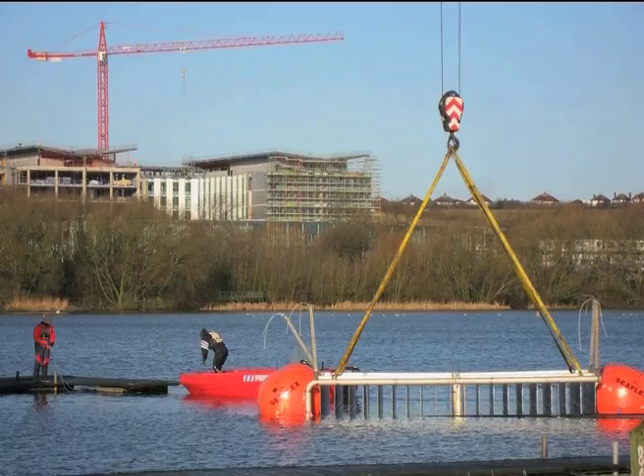Or in the summer, when the lake is cooler than the outside air temperature, it provides cooling to the hospital. It's very, very energy efficient, much more efficient than coal or oil or any traditional technology. Because for every 1 kilowatt of power that you put into the system, you get between 4 and 7 kilowatts back again, which means that you have far better CO2 emissions, but also there's lots of cost savings there for the NHS for many, many years to come.